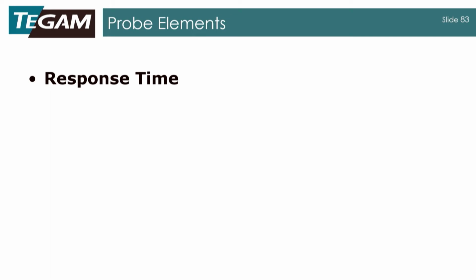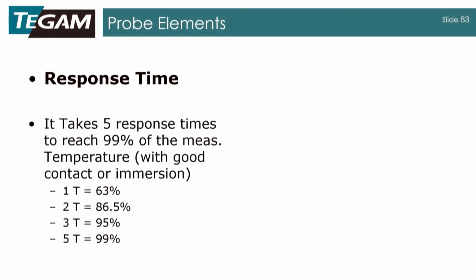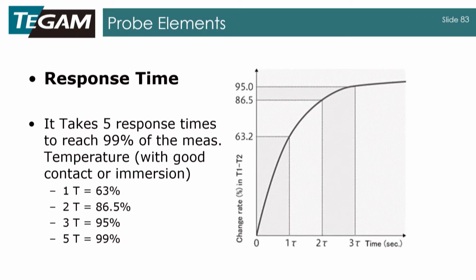So next we're going to talk about response time. And response time is, for anyone that's familiar with how a capacitor charges up, this is a first order system as well. And it's going to take 5 response times to reach 99% of the measurement temperature. And there's your graph there. And the response time is directly related to your thermal mass. So basically, the more mass you have in your probe, the longer the response time. And we have a demo here that we'll set up.